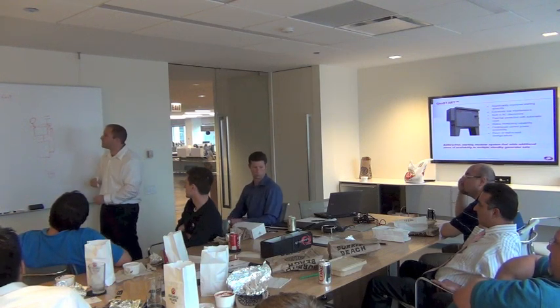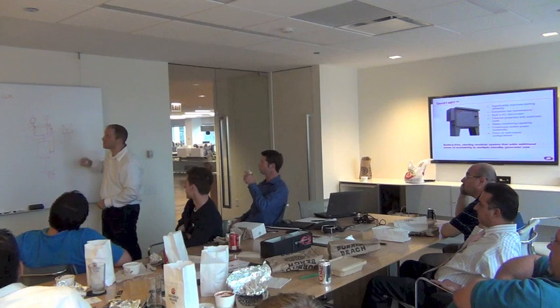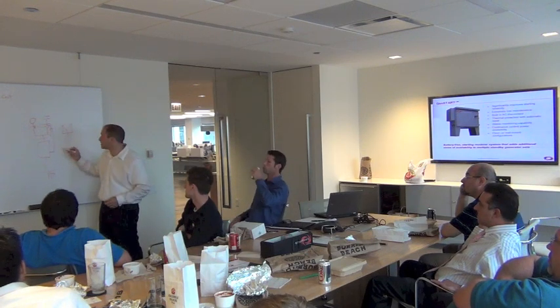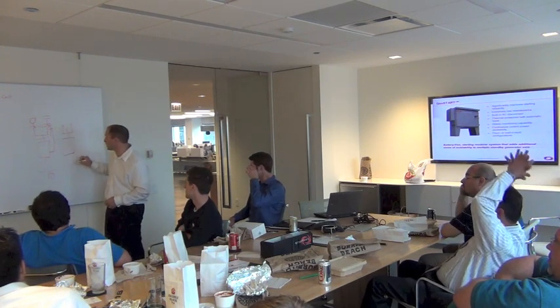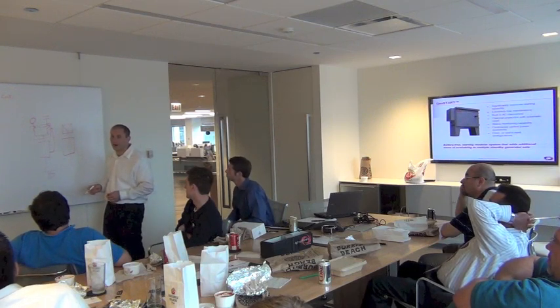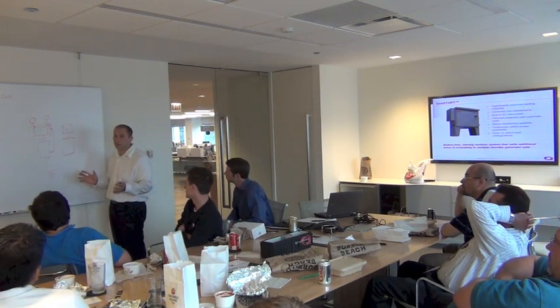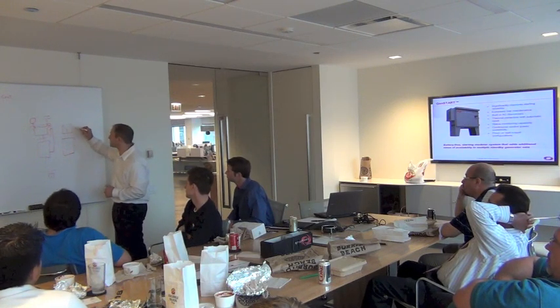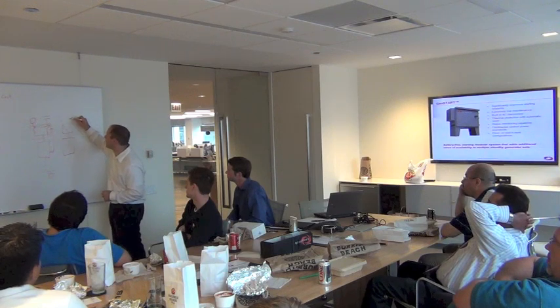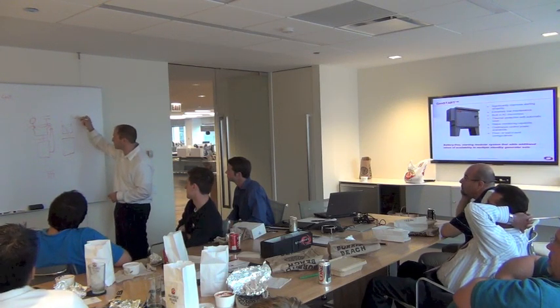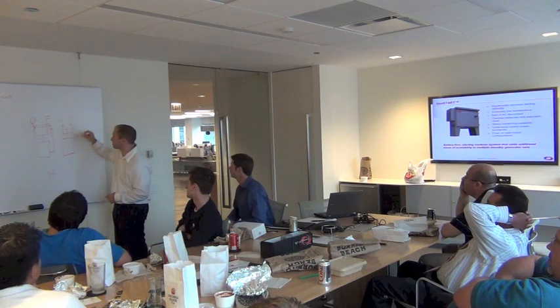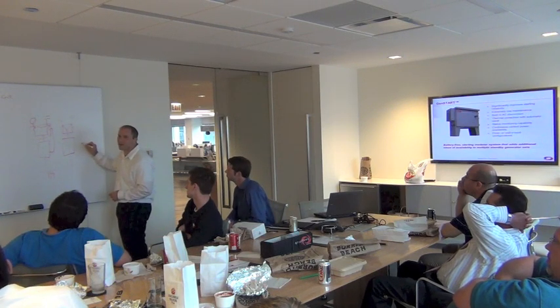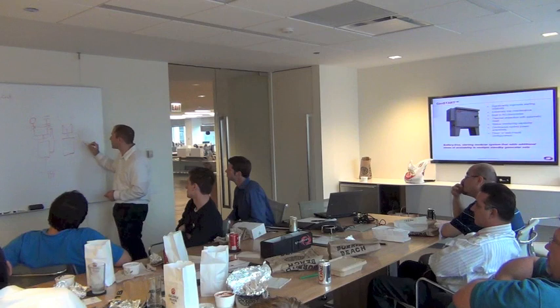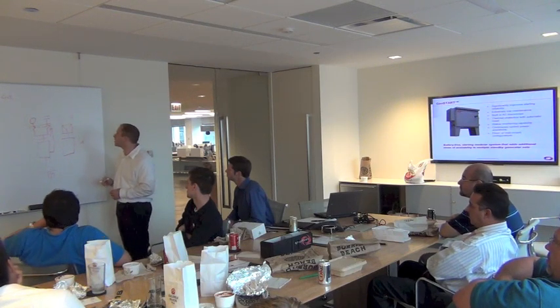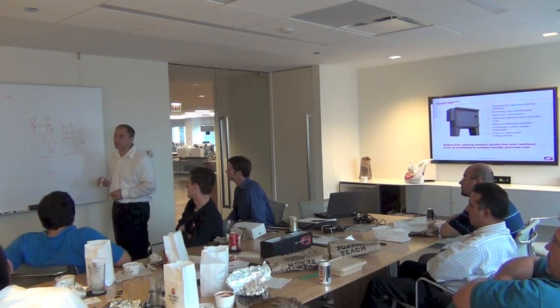Where that comes in handy is if you have a transfer switch, for example, maybe it's existing and it doesn't have overvoltage detection. Maybe you have an overvoltage situation, and your UPS goes into discharge. With flywheels, you are limited around ride through time, so obviously you want to design around it. If you design around it correctly, there's no doubt you can build a reliable system, if not more reliable than a battery-based system. So you have an overvoltage situation, your transfer switch doesn't see it, we go into discharge, and we'll define that in commissioning. We'll say, okay, 80%. We know if we have 80% energy, that gives us enough time to transfer to the generator and walk the load on. So that's a nice integration feature that we have that our competitors don't use.